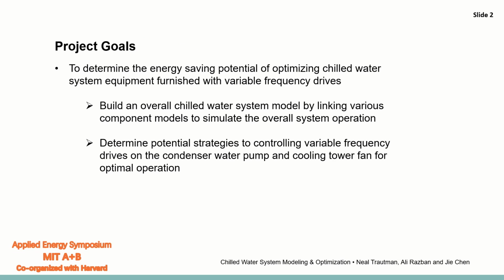So the goal of this project was to determine the energy saving potential of optimizing different pieces of equipment in a chilled water system that are equipped with a variable frequency drive. In order to do this, we built an overall chilled water system model by linking together various component models in order to simulate the overall system operation. And additionally, we wanted to determine if there were any potential control strategies that we could use to control the variable frequency drive on the condenser water pump and on the cooling tower fan in order to achieve optimal operation.